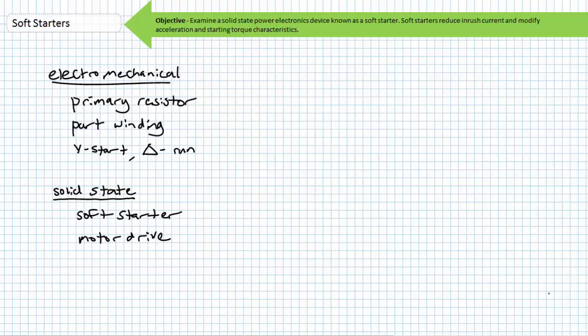It is for this reason reduced voltage starting methods are employed. Reduced voltage starting methods include, but are not limited to, electromechanical means like primary resistors, part windings, Y-start, and delta run starters, and solid-state means like soft starters and motor drives. All these methods serve to limit inrush current and limit mechanical stresses to the driven load. Today we'll discuss one of these methods, soft starters.